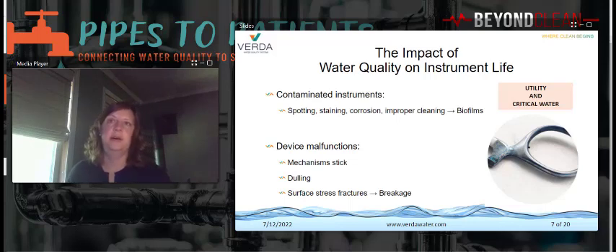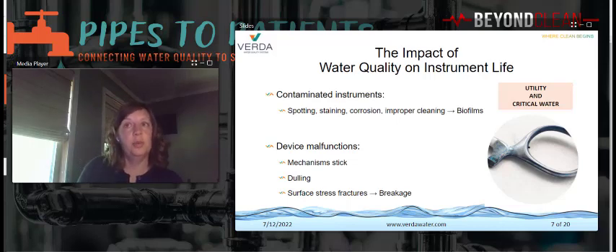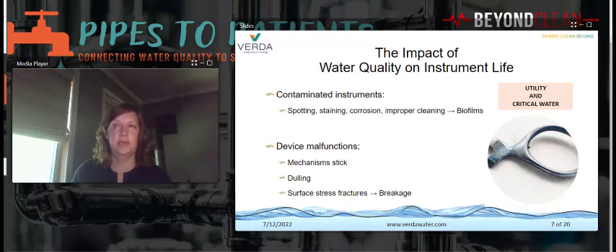So let's talk about some of the malfunctions due to water quality. For example, a hemostat may not open because of corrosion in the box area. Mechanical movement of the device could be obstructed by residual debris inside the mechanism. Corrosion could result in scissors and scalpels becoming dull and pitted. They won't cut with a sharp edge. Instruments then have to be resharpened more frequently, prematurely retired, adding to the cost of the department.